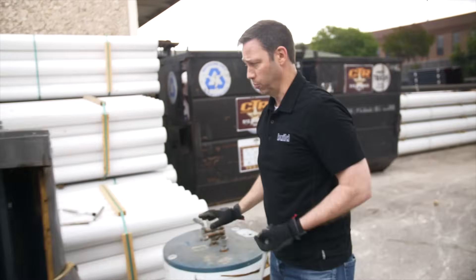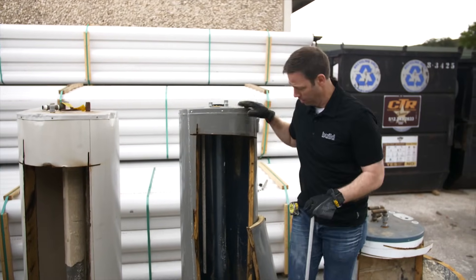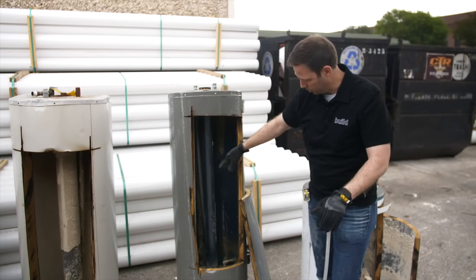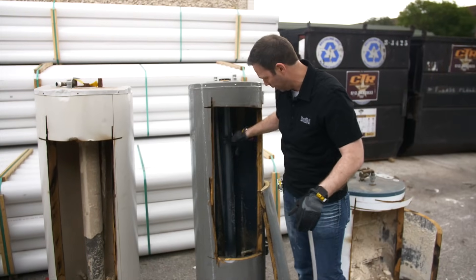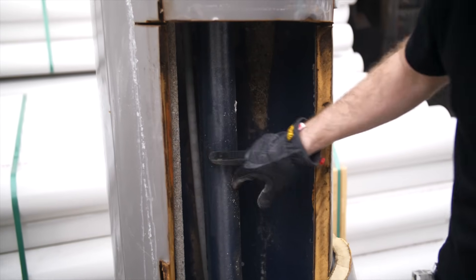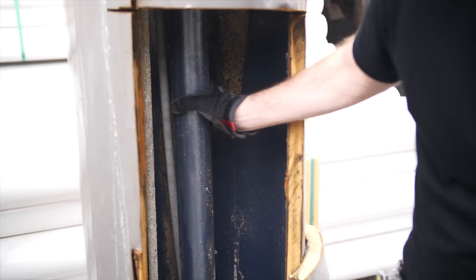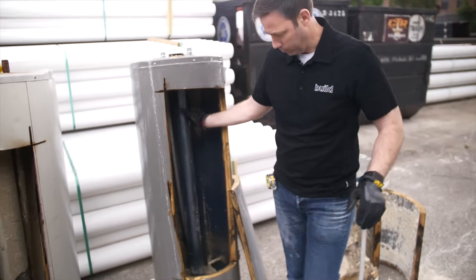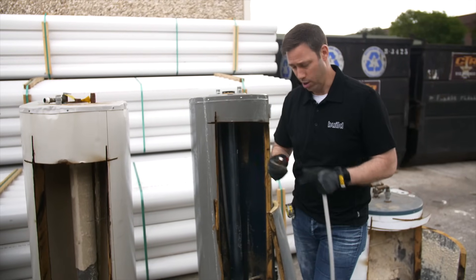Next tank — moving from the oldest to the newest. This model is a 2016, so it's only two years old. I have no idea why this one got replaced. If you look on the inside of this tank, the metal looks like it's in fantastic condition — real good shape. It looks almost like a baked-on finish on top of this metal, so the manufacturer did a real nice job preventing rust. We did have a little bit of scale in the bottom of this tank if you saw the other video, but very little scale overall.